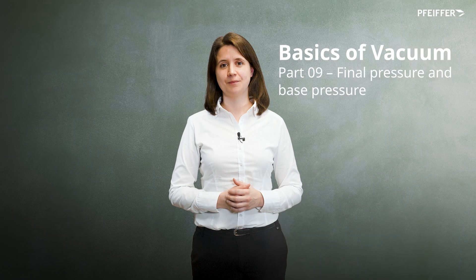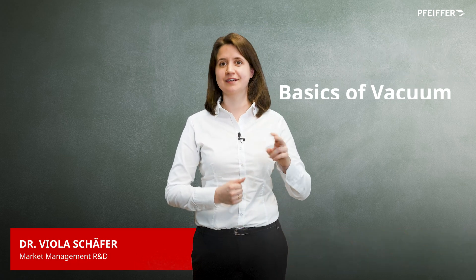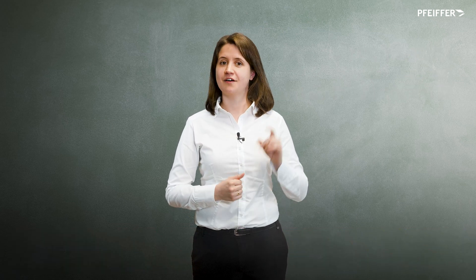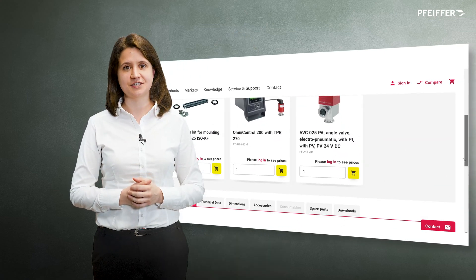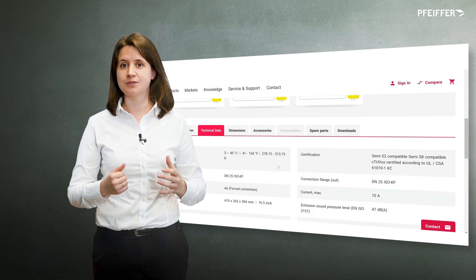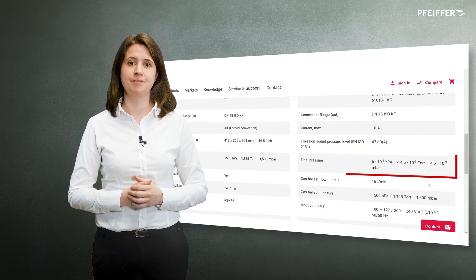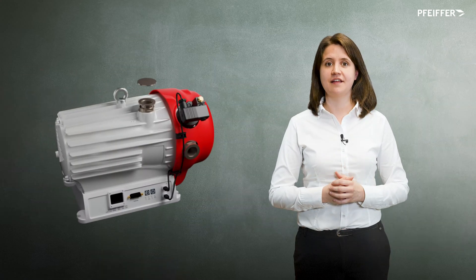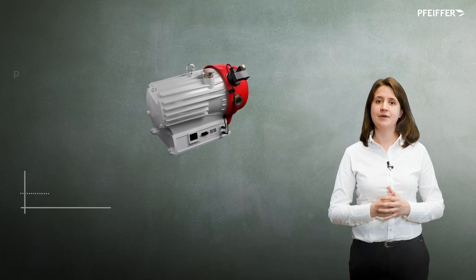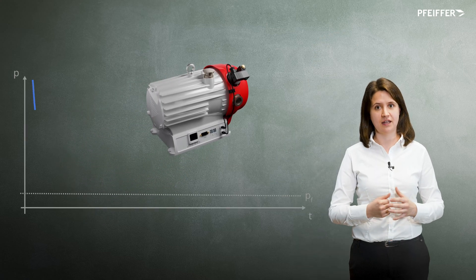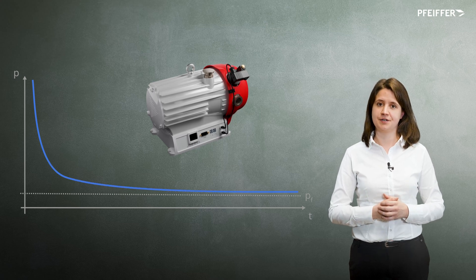Hello and welcome to Pfeiffer Vacuum. My name is Viola, and in this video today we discuss two important characteristics of vacuum pumps: final pressure and base pressure. When reading the specifications of vacuum pumps you will almost always find it — the final pressure, also called ultimate pressure. This is the lowest pressure that a blind-flanged vacuum pump can achieve. The pump reaches the final pressure asymptotically, and there are firmly defined boundary conditions for the final pressure.